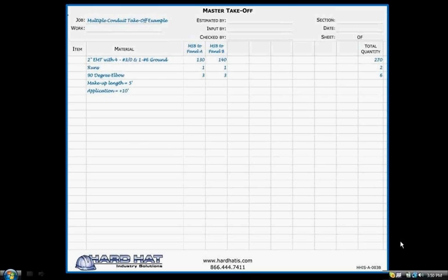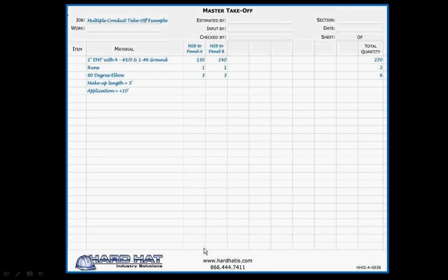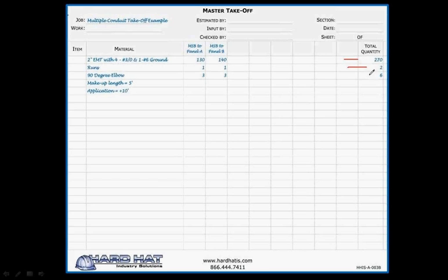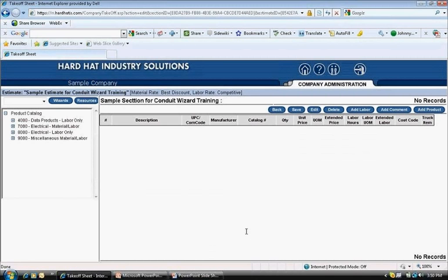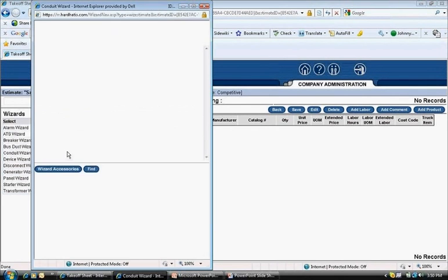Again, here's the takeoff sheet. I'll enter the total amount of conduit feeding both panels at one time. The way to accomplish that is to enter the total amounts of footage, number of runs, and total elbows at one time, or in this case 270 feet of conduit, two runs, and six elbows, or 90s. I will now use the Conduit Wizard. I click on the Wizards button and select Conduit Wizard and the wizard pops up.